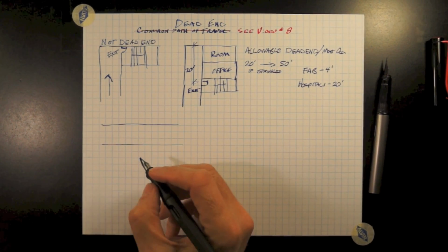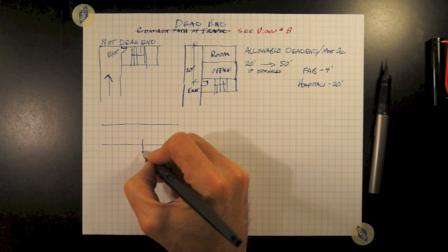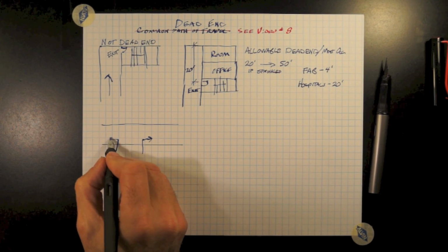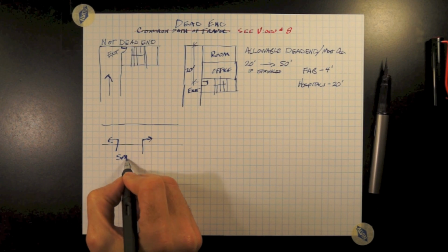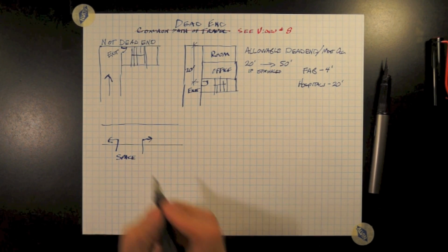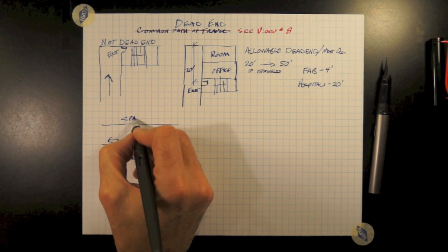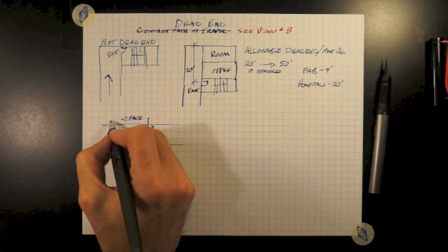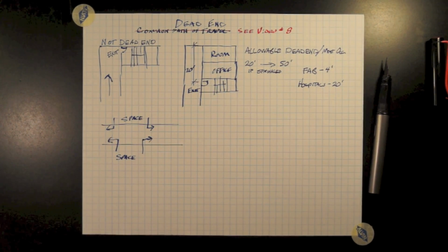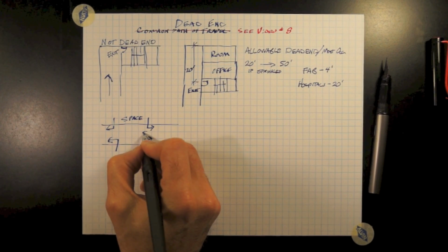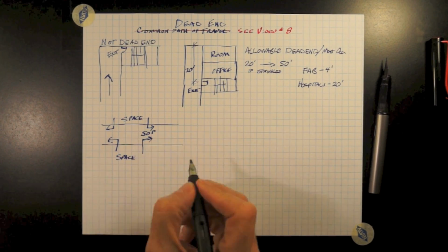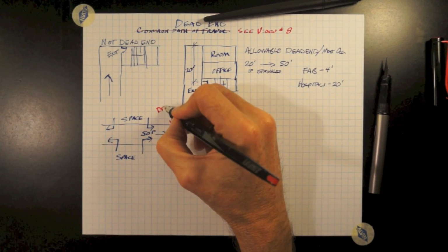So now let's look at a general corridor/hallway and where we have a number of offices exiting off that corridor or hallway. If the occupant load of those spaces on either side of the corridor, and you're having 2 directions to travel, is greater than 50 persons, the door cannot swing against the people that are traveling toward it. Therefore, the door must swing in the direction of travel.